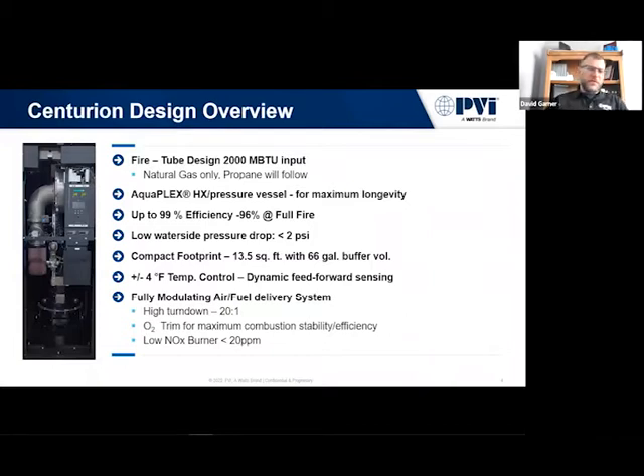And one of the new features that we have is our feed-forward control temperature system, that this unit can control the discharge water temperature plus or minus 4 degrees, which is the same as your master mixing valve. And as I talked about earlier, it's a high turn down unit, it has a 20-to-1 turn down. So it's a 2 million BTU input, and that means it can turn all the way down to 100,000 BTUs. That's pretty much what you're using for a residential domestic heating load in your house.